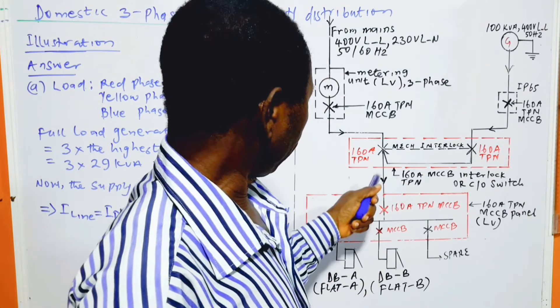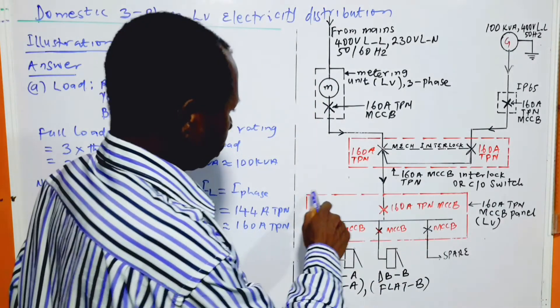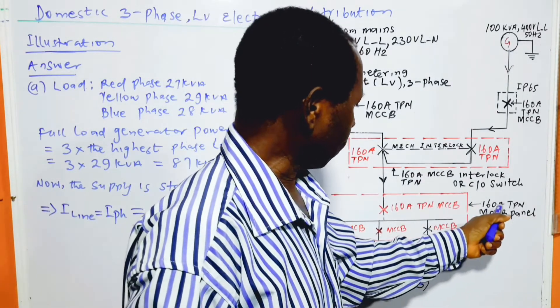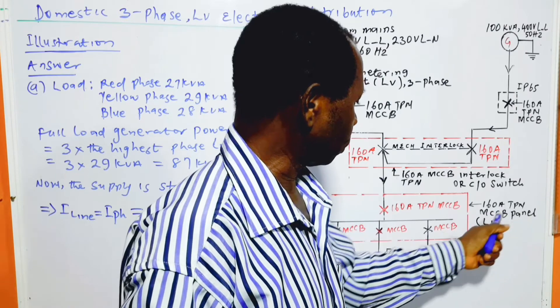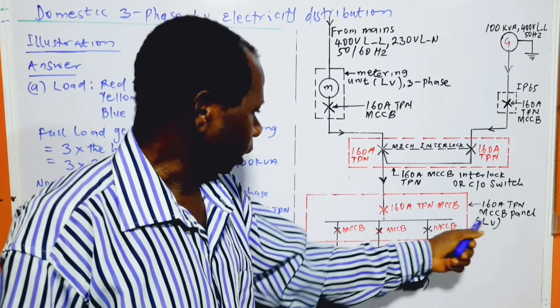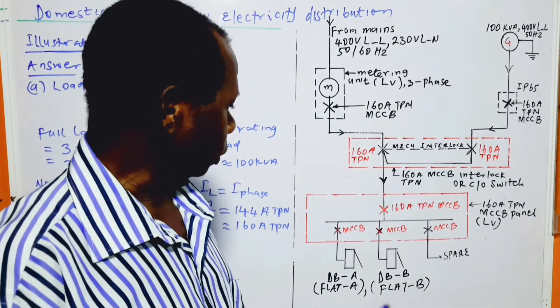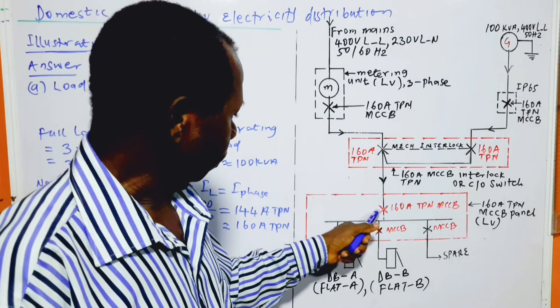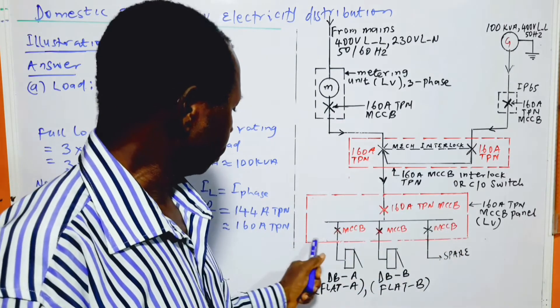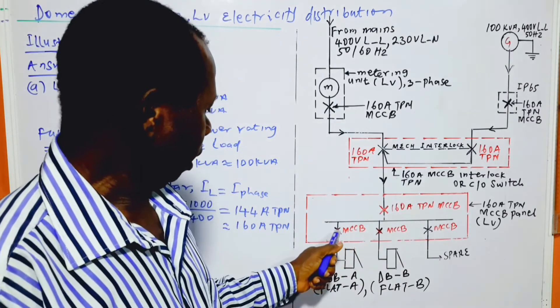We move on. This is the load panel, which is also 160 amp triple phase with neutral MCCB panel, low voltage panel of course. This is 400 volt line to line and 230 volt line to neutral. We have the incoming to the panel being 160 amp triple phase MCCB, and we have the outgoing circuit breakers.